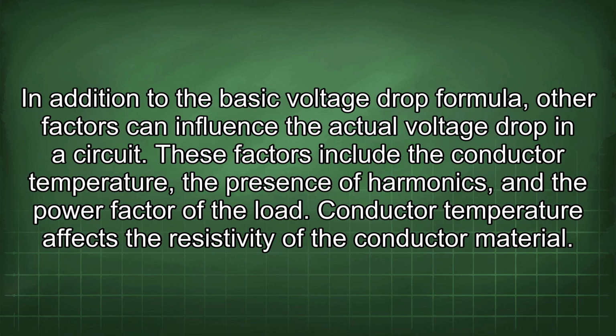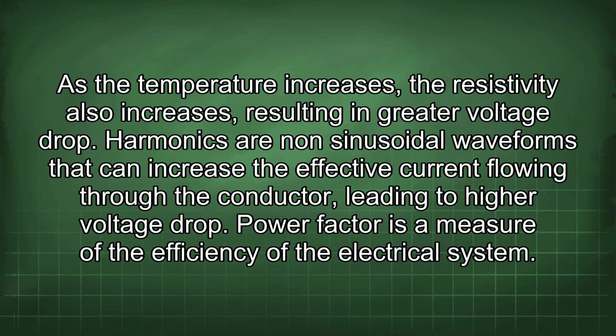In addition to the basic voltage drop formula, other factors can influence the actual voltage drop in a circuit. These factors include the conductor temperature, the presence of harmonics, and the power factor of the load. Conductor temperature affects the resistivity of the conductor material. As the temperature increases, the resistivity also increases, resulting in greater voltage drop. Harmonics are non-sinusoidal waveforms that can increase the effective current flowing through the conductor, leading to higher voltage drop.